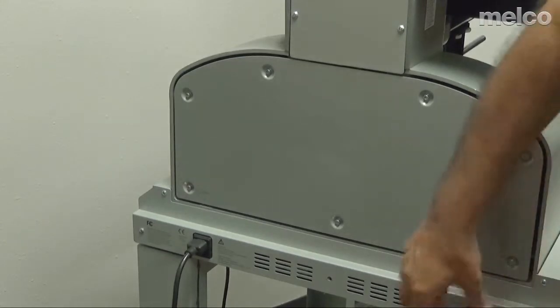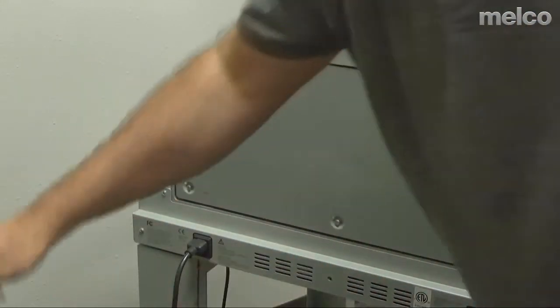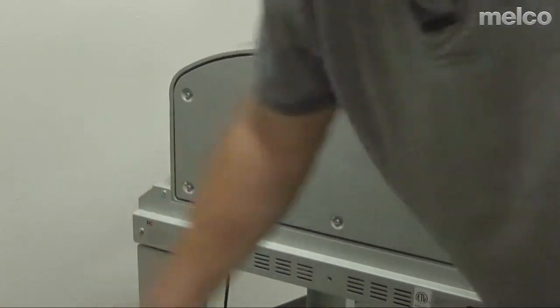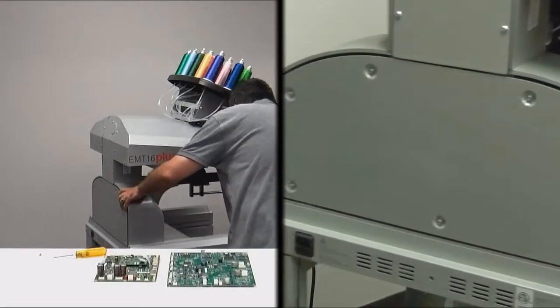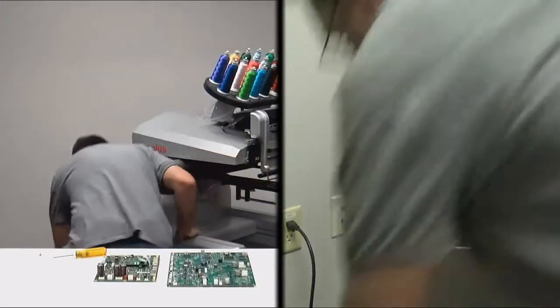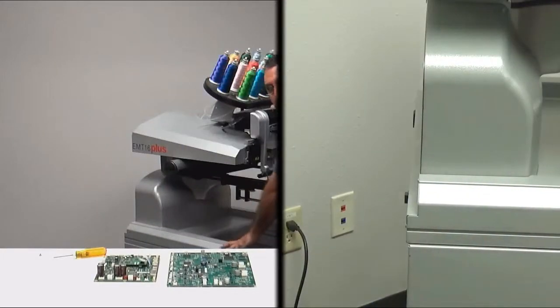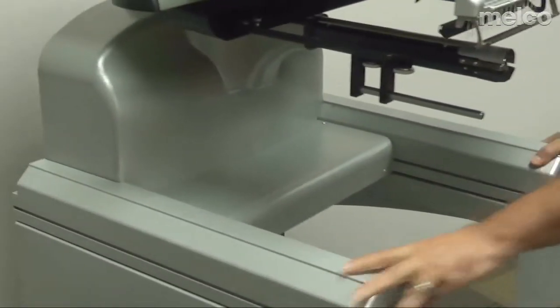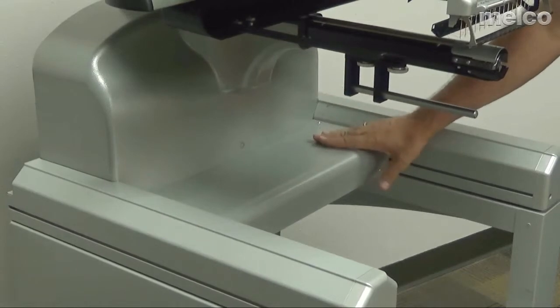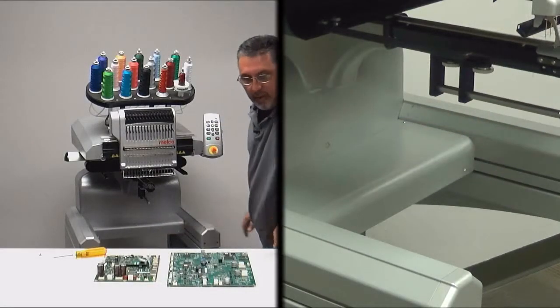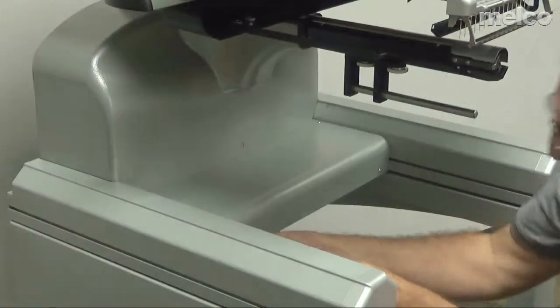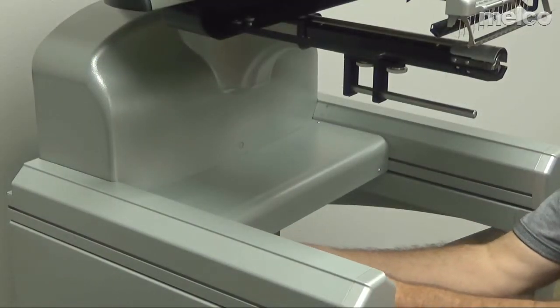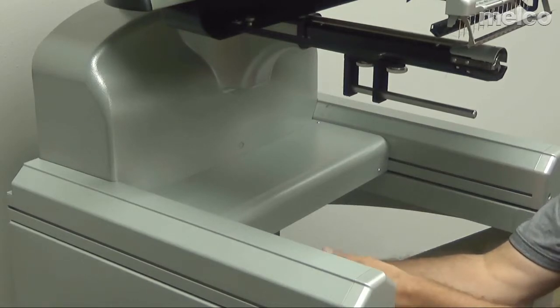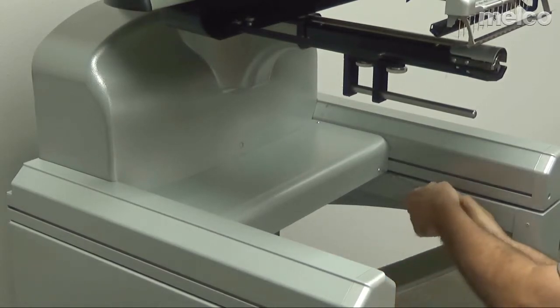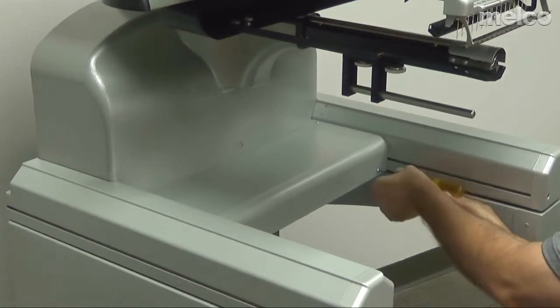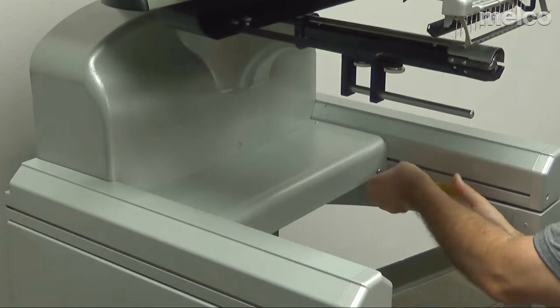And while we're back here, we're going to go ahead and disconnect our Ethernet connection and our power cord. That's all we're going to be doing in the rear of the machine for now on the main board replacement. So what we're going to go to now is we need to remove this access cover. That is held on by 4 button head Allen screws that you would use a 2.5 millimeter Allen wrench. And again, in your operator's kit for the machine, you are set a bent Allen wrench set.